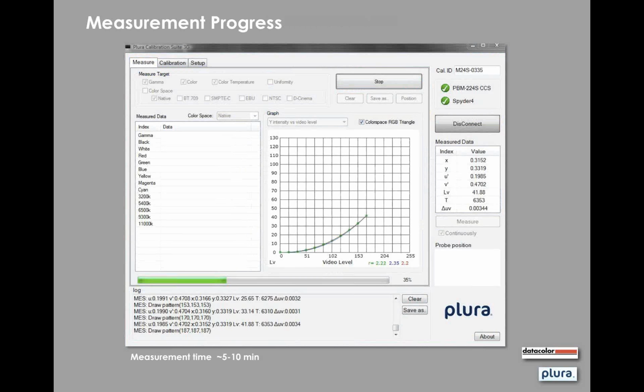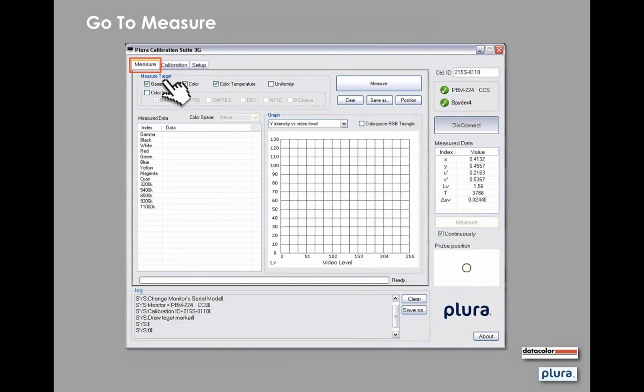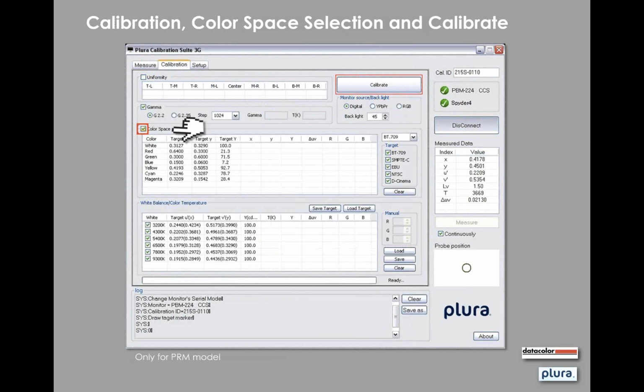Now, I want to back up a minute. I forgot to mention something. I'm going to back up several slides here. Okay. When we click on Calibrate, that calibration cycle, I neglected to mention this. The calibration cycle is going to take 20 to 30 minutes. So it's going to run through the sequence that you would normally expect to see. It's going to run a bunch of colors, et cetera. And the colorimeter is going to read the values of those colors as displayed by the PBM or the PRM display, and it's going to log them and then do an analysis.